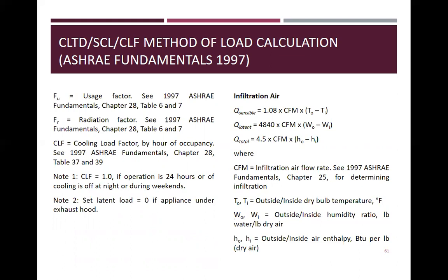Infiltration air. Next. Q sensible is 1.08 times CFM times T sub O minus T sub I, outdoor minus indoor. Q latent is 4840 times CFM times W sub O minus W sub I. Q total is 4.5 times CFM times H sub O minus H sub I. Take note, that 4.5, the exact value is 4.54. The one who used that, this Q total is more accurate than this Q latent. So the 4840 of Q latent is an approximate.